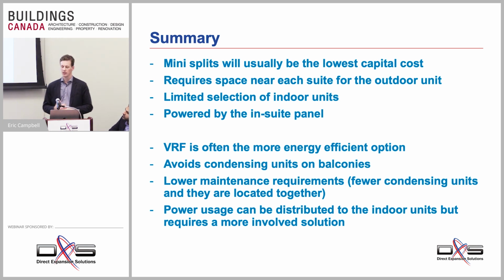And lastly, power usage. Again, there's the electrical side of the condensing units on the roof, that you need to provide, which is an extra cost. One thing I did want to mention is that we can do metering for VRF solutions. It is a little bit more involved, and we need to work with a billing company to do that. But there is a way to divide up the power usage of that outdoor unit amongst all the indoor units.